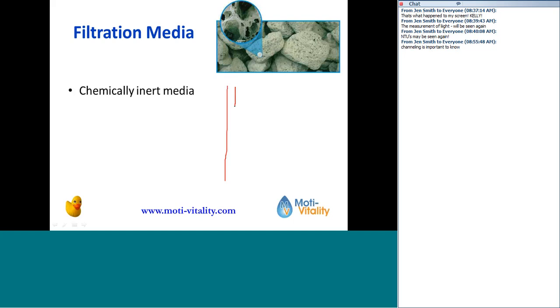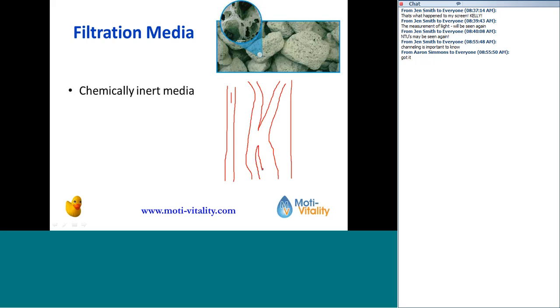Let me show you what channeling is. If this is the distributor tube, and you've got all the media in here, what channeling does is it forms these ant hills. Water comes down and forms these little ant hill paths through the media. If you ever look at the inside of ant hills underground, the water will just flow right through these paths, and it won't really be filtered. That is caused from inadequate backwashing. That's what's going to happen when you form those mud balls. The water's just going to go right through there.